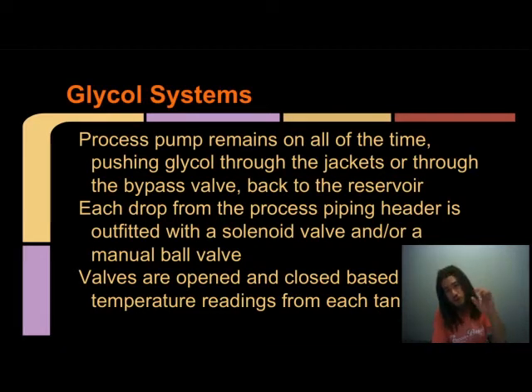So you'll have a thermal well that'll have a digital thermometer in it usually that'll then go to a control panel. And on the control panel, you can set a temperature. If the temperature goes a little warm, the solenoid valve will open up, allowing the glycol to flow through, because the glycol is always flowing. The process pump's always going. When it's cool enough, or it's a little too cold, it'll kick off the solenoid valve. Glycol doesn't go to that tank. It just passes that tank now because it can't go through the solenoid valve that's closed.